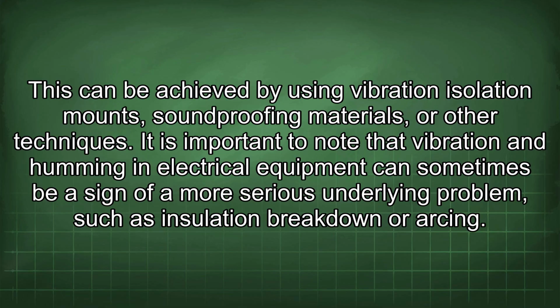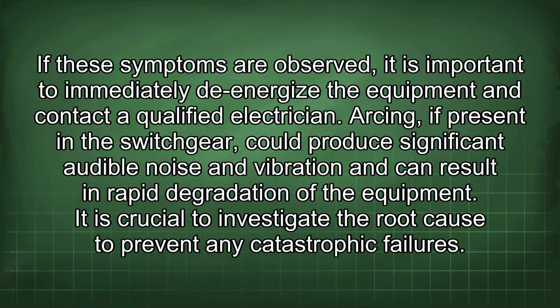It is important to note that vibration and humming in electrical equipment can sometimes be a sign of a more serious underlying problem, such as insulation breakdown or arcing. If these symptoms are observed, it is important to immediately de-energize the equipment and contact a qualified electrician. Arcing, if present in the switchgear, could produce significant audible noise and vibration and can result in rapid degradation of the equipment. It is crucial to investigate the root cause to prevent any catastrophic failures.